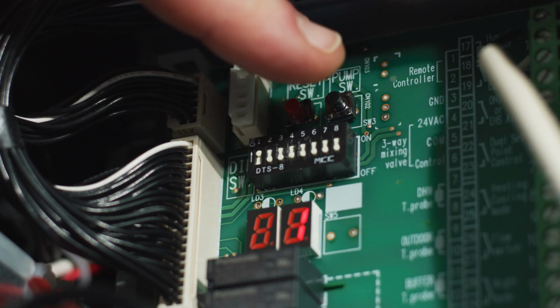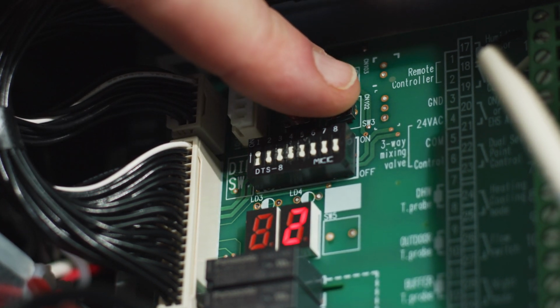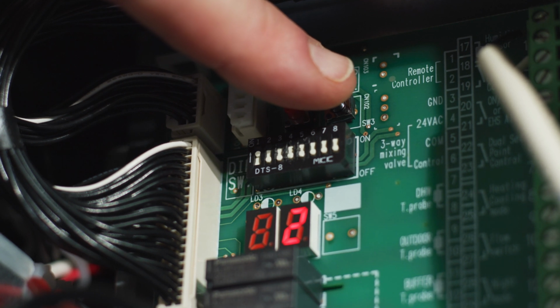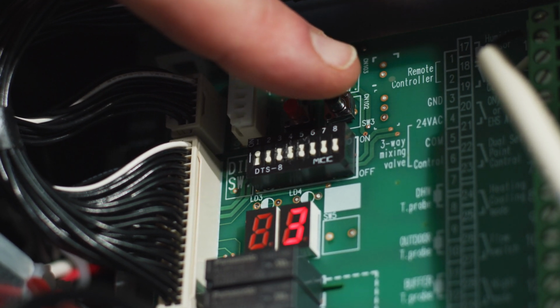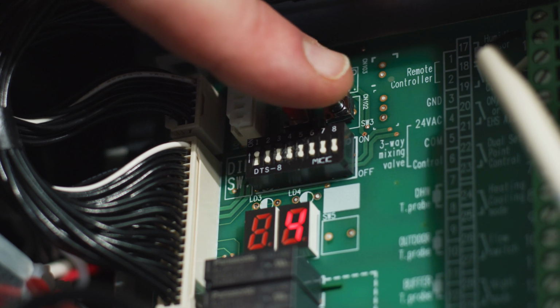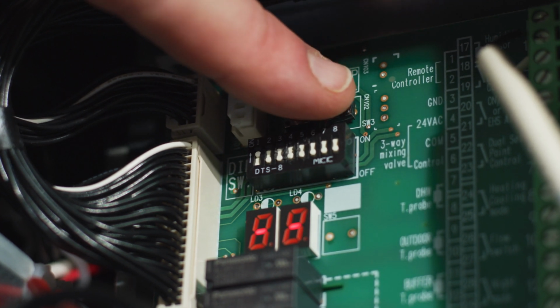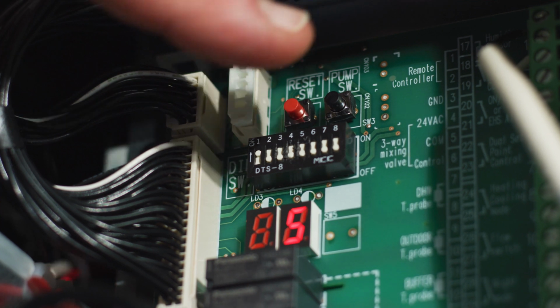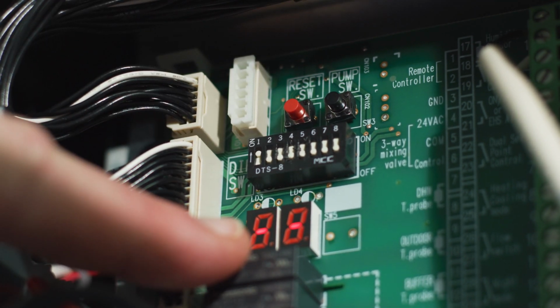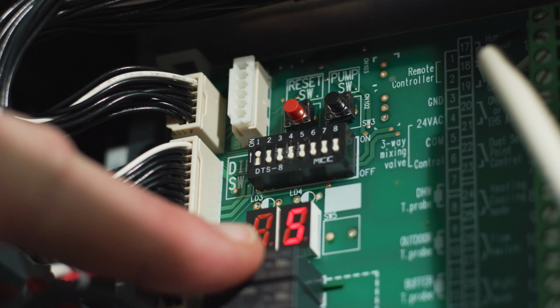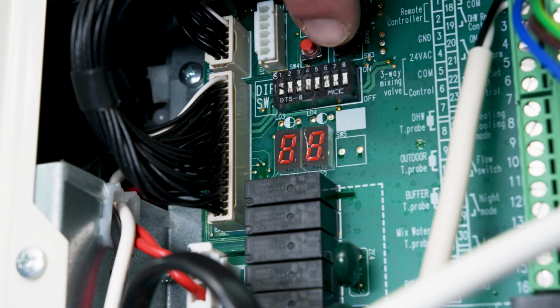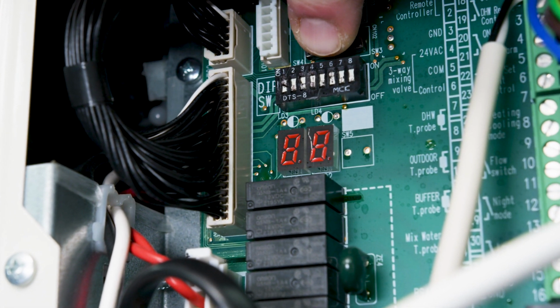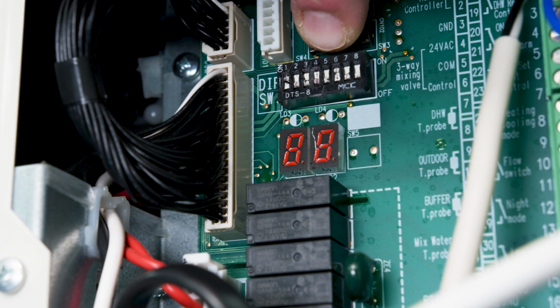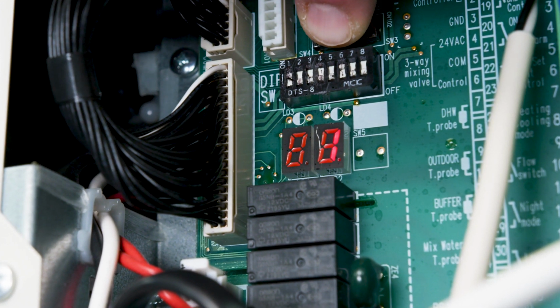Another useful function is an error history display, which can show the previous 10 error codes. This information is not available on the remote controller. It can only be viewed on the terminal PCB on the unit and is given numerically showing the latest error code first. If there is no history of an error, the display will show two dashes. To gain access to this information, press and hold the black pump switch and red reset switch. They can be found directly above the 8 dip switches on the terminal PCB. This information is particularly useful for diagnostics and pinpointing recurrent issues.